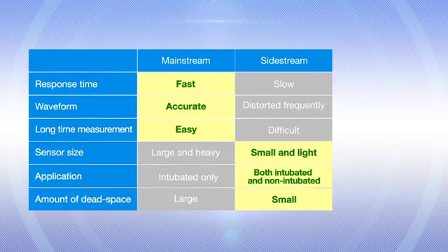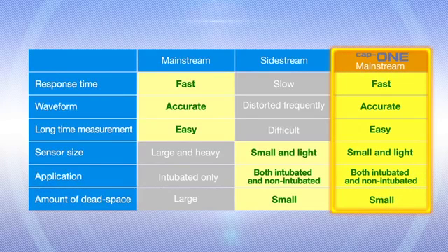Advantages of mainstream sensors are rapid response, less waveform distortion and few measurement interruptions. But compared to sidestream sensors, mainstream sensors are heavier, limited to intubated patients and have larger dead space. Now cap-ONE has overcome these disadvantages and maintains all the advantages of the mainstream sensor for the optimal capnography.